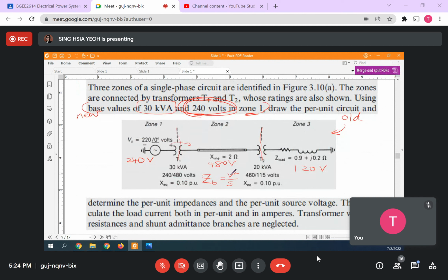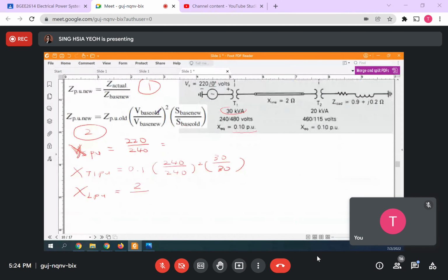Anyone can tell me what's the V value here? In zone 2, you have to use 480. So it's 480 power 2 divided by the S value 30K. So once you get your Z base, then you put it in here. Then you get your X line PU value, okay?